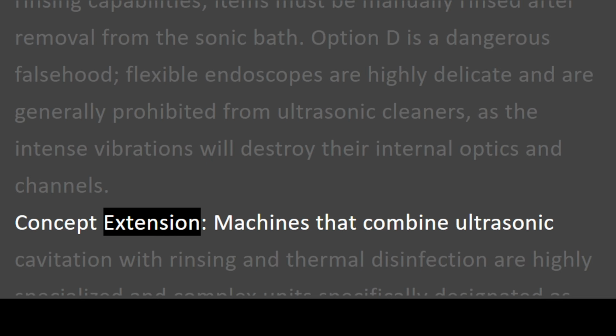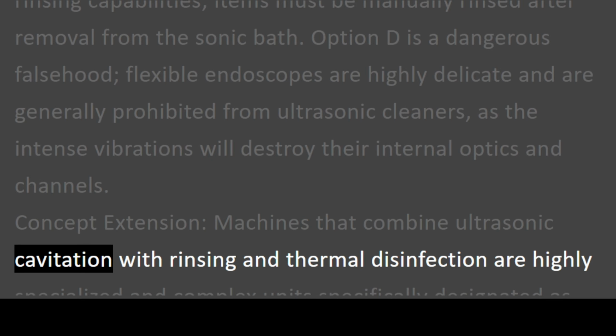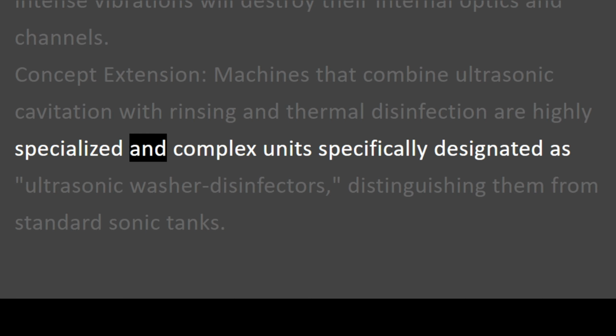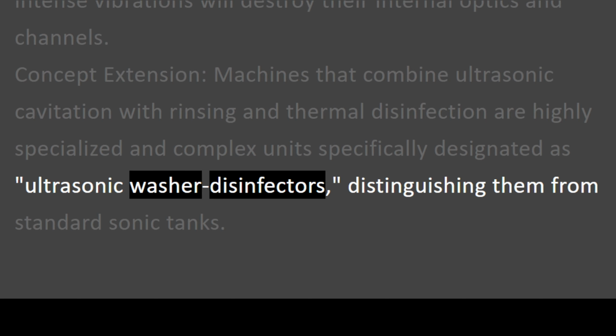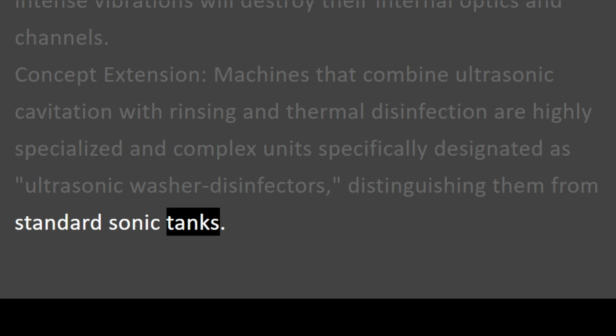Concept extension. Machines that combine ultrasonic cavitation with rinsing and thermal disinfection are highly specialized and complex units specifically designated as ultrasonic washer disinfectors, distinguishing them from standard sonic tanks.